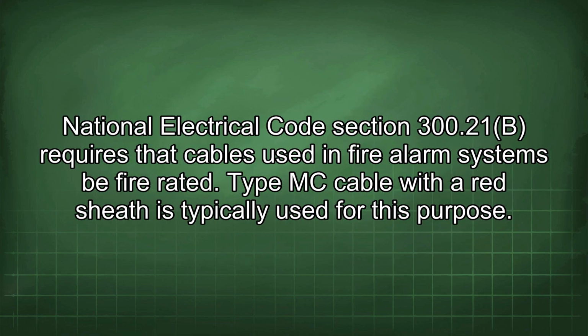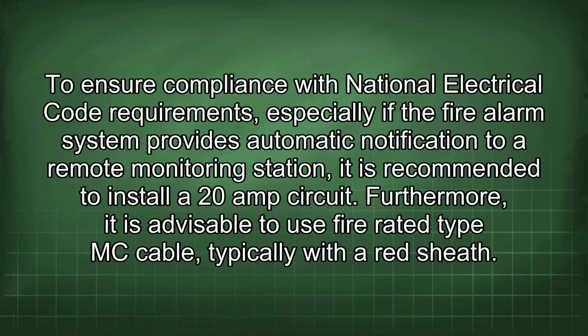National Electrical Code Section 300.21b requires that cables used in fire alarm systems be fire rated. Type MC cable with a red sheath is typically used for this purpose. To ensure compliance with National Electrical Code requirements, especially if the fire alarm system provides automatic notification to a remote monitoring station, it is recommended to install a 20-amp circuit.